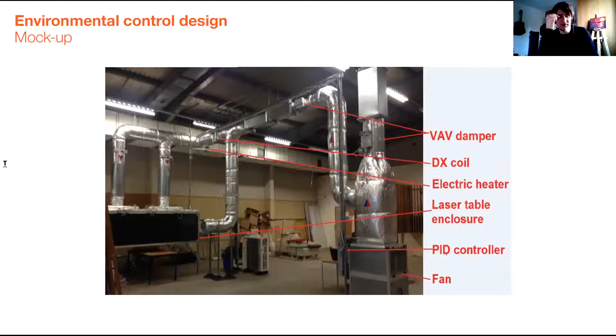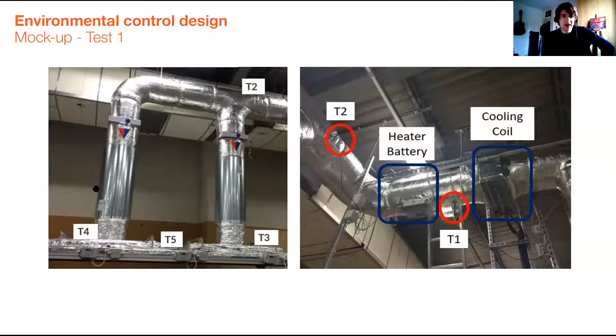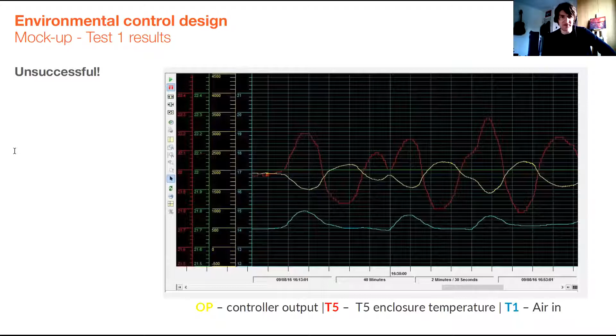And on the next slide, you can see we positioned a number of temperature sensors. We gave them all a number, temperature T1 to T5, and we were going to monitor exactly what was going on at each point of the system. The key thing was that we would achieve the stable condition at T5, which is a temperature sensor actually within the enclosure. So we did a first round of testing, and it was pretty unsuccessful actually. You can see the different colors represent different temperature sensors, and there are some pretty significant oscillations in temperature, swinging around beyond a degree, so well beyond the brief of plus or minus 0.1.